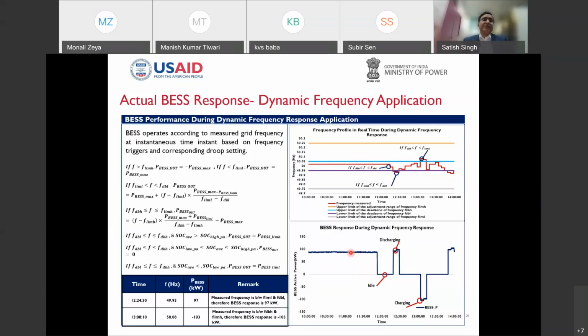But this response we are getting because there is a SOC kind of phenomena, that state of charge of the battery should be honored. Whenever a battery is supposed to be in idle mode, it is also looking into the state of charge numbers. If my state of charge numbers are below or high, the battery would try to compensate and make the state of charge numbers between the pre-specified values. So here the output should have been idle, but there are a few values. I'll discuss in the next slide then.